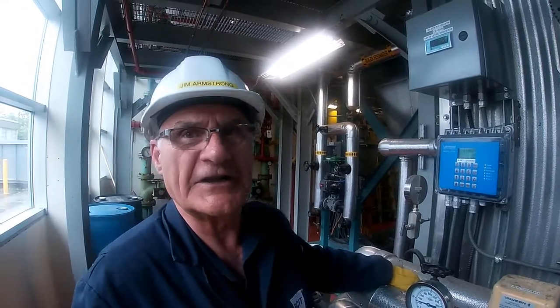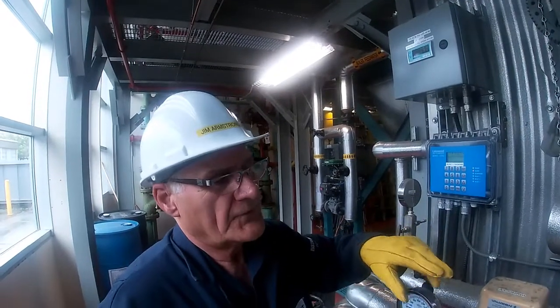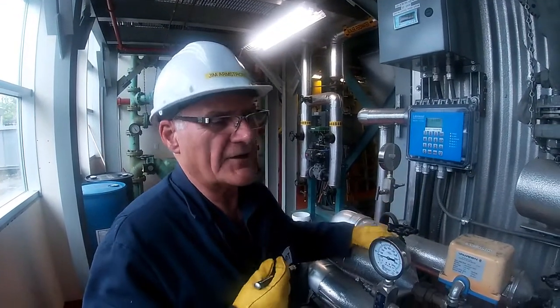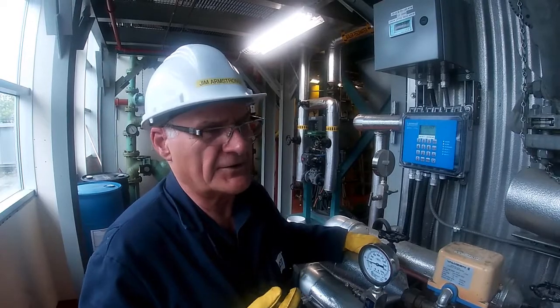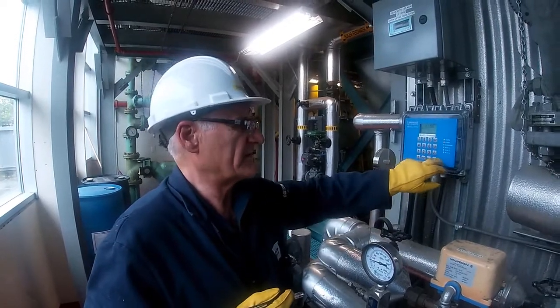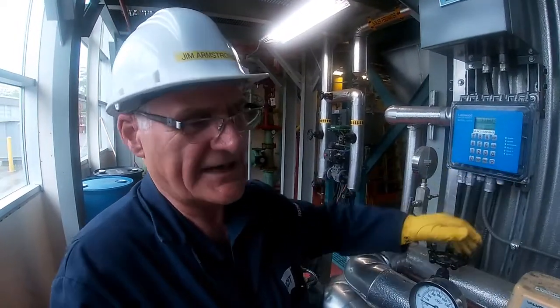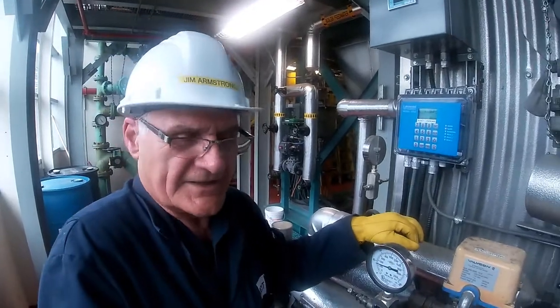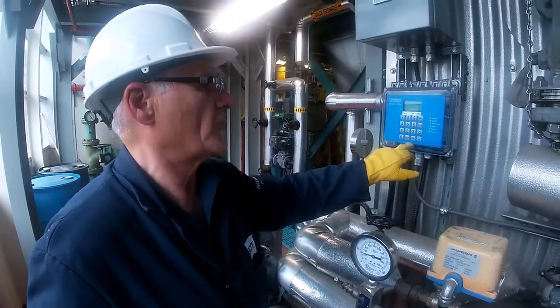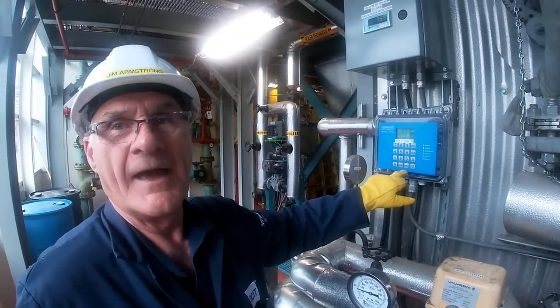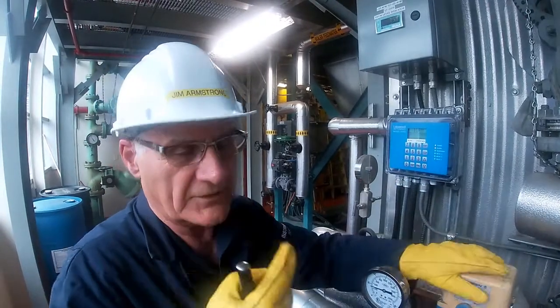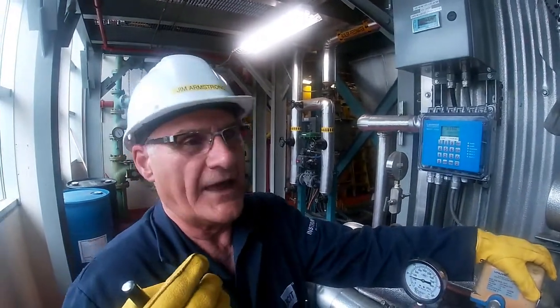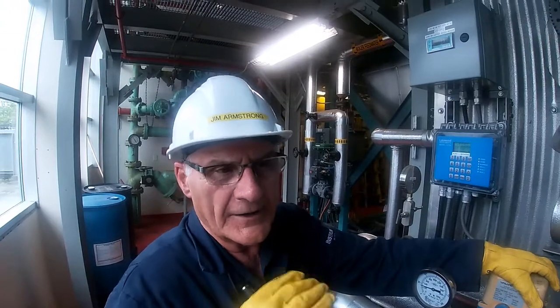It is raw conductivity. So normally it's somewhere around 1800 microsiemens per centimeter. So what we'll do is we'll actually take a sample of the water, see what the conductivity is, and then go through a single point calibration on here. Just like you would do with a nuclear density gauge, or with a refractometer, to basically zero it to the process. We do the same thing with this guy.